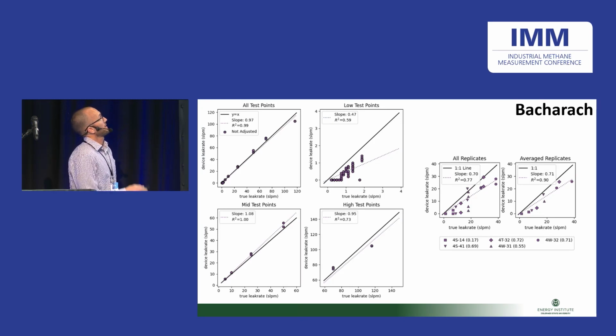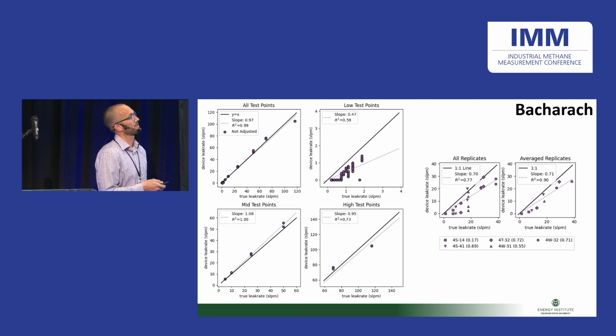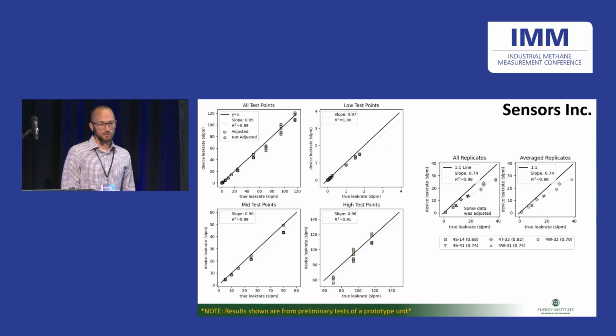So for the Bacharach, generally pretty good as the incumbent here. Good linearity over the whole range. Kind of poor performance at the low end, and then with the real equipment, a lot of variability and a generally low bias. And that was kind of common with some of the other ones too.